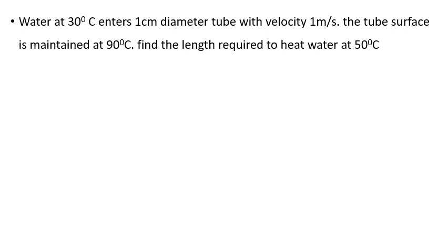Moreover, the surface temperature has been given, which means we can see three temperatures in the problem. So we have to use the LMTD concept. LMTD concept means 90 degrees minus 30 degrees can be used for theta i, and 90 minus 50, that is 40 degrees, can be used for theta naught in our LMTD calculation.